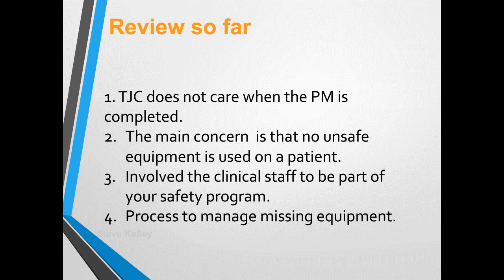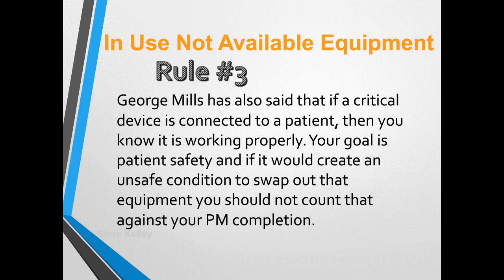Rule number 3: in-use, not-available equipment. George Mills has also said that if a critical device is connected to a patient, you know it's working properly, and your goal is patient safety. If swapping out that equipment would create an unsafe condition, you should not count that against your PM completion.